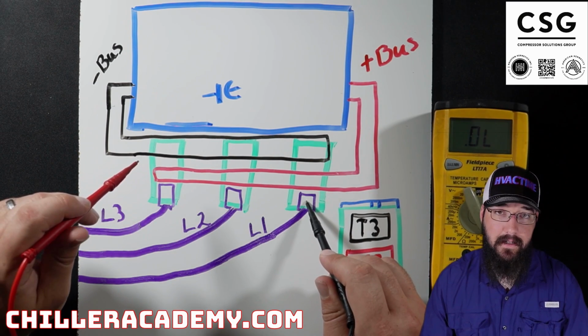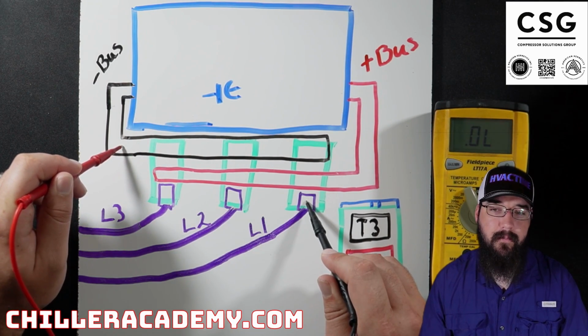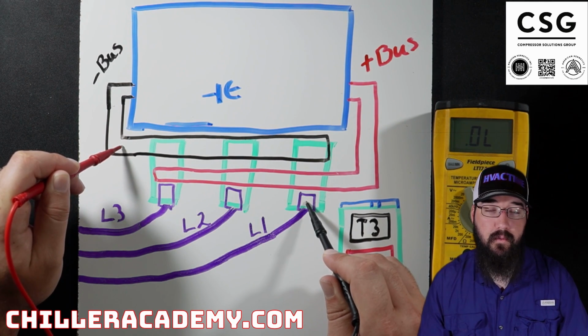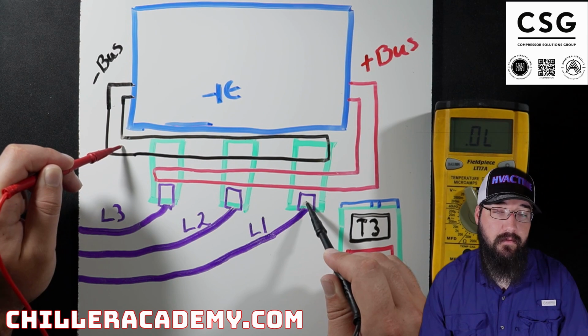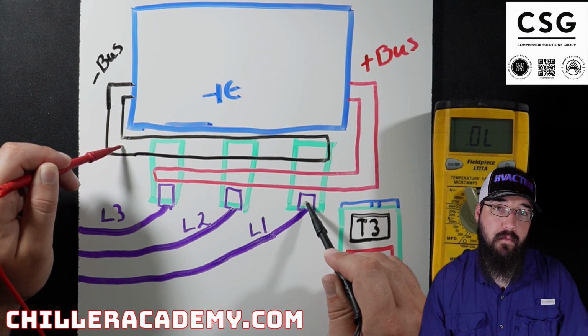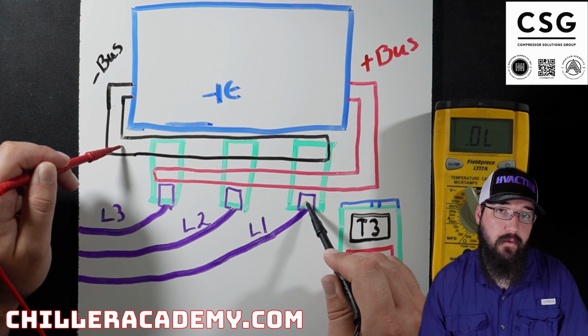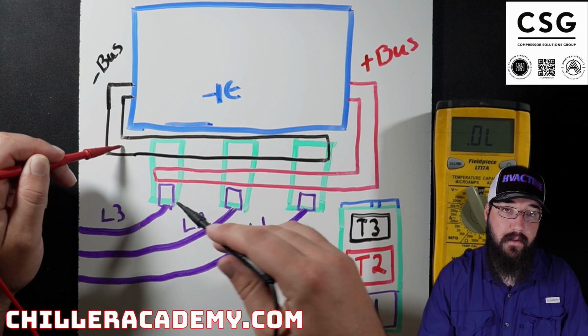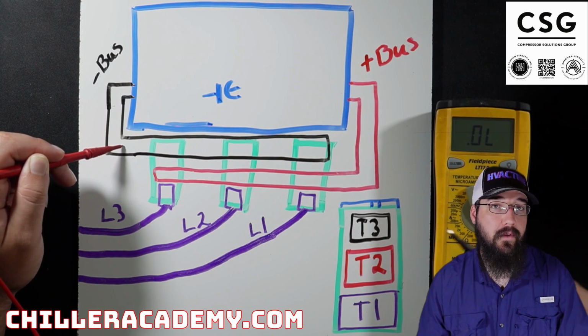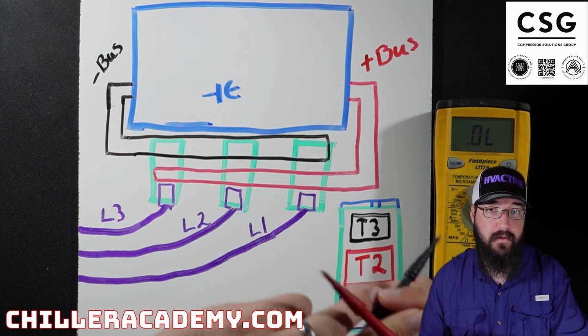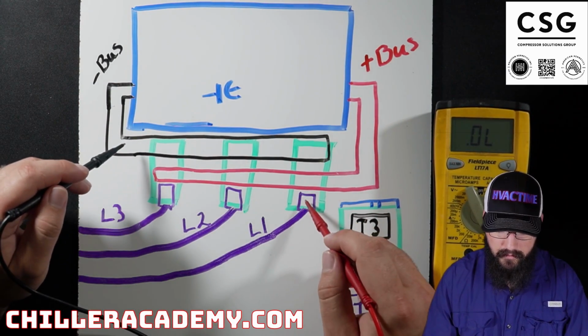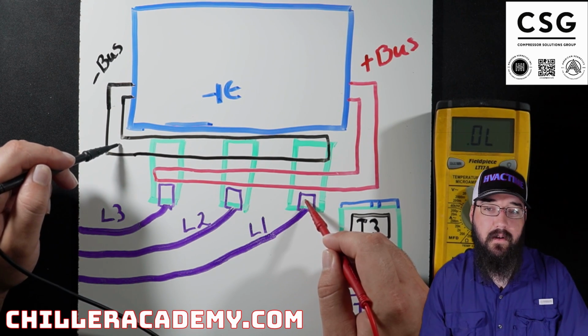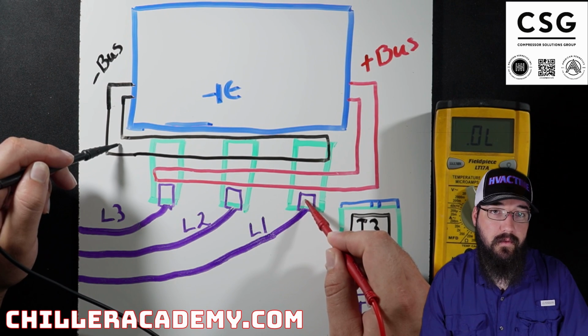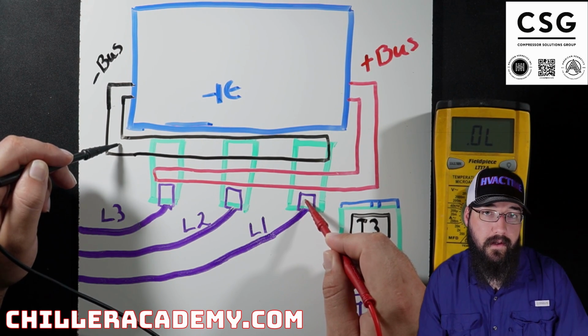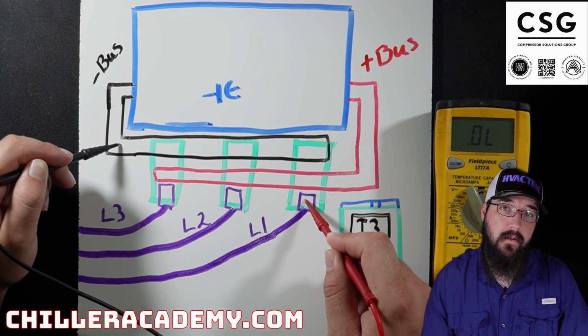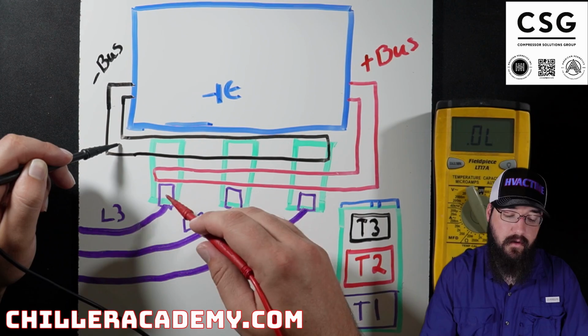Now, this next test for the negative bus gets a little different. First reading, we're going to put our black lead on T1 and the red lead on the negative bus. This is going to give us a 0.3 to 0.4 VDC reading, which on an analog in ohms would be a 5 to 15 ohm value. You would do that same test across and get that same result of 0.3 to 0.4. Now, when you reverse your leads, pay attention to this. When red goes on T1 and black on the negative bus, you go back to the previous results of 2 to 3 VDC or OL. It could be either. And then you would just take your readings across and make sure they all match.